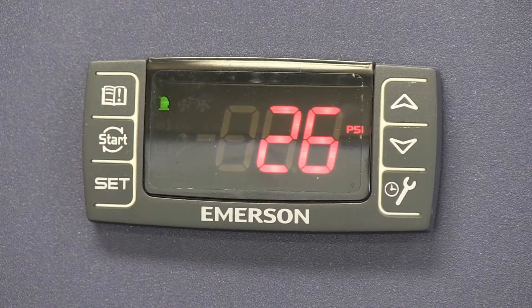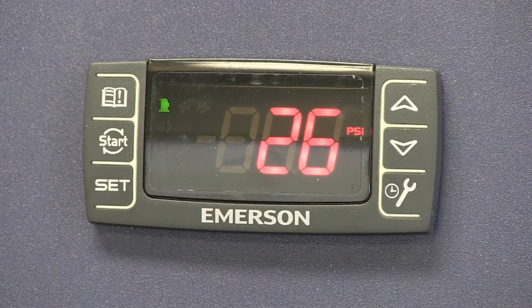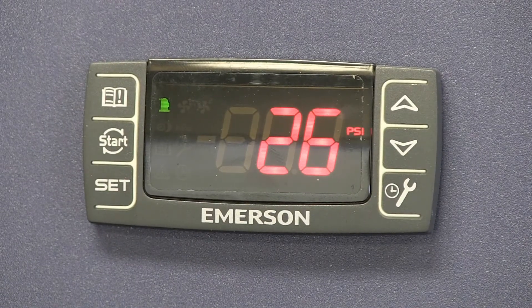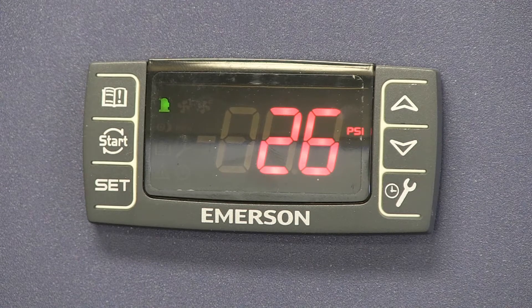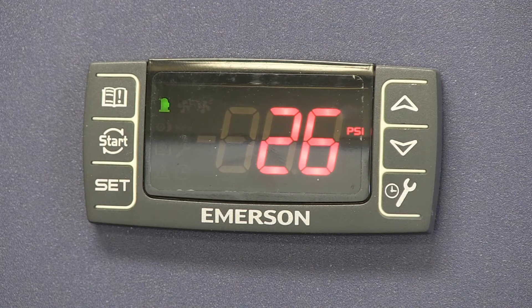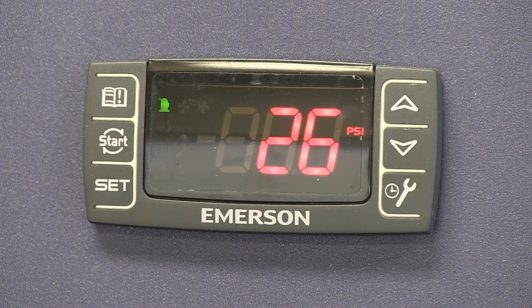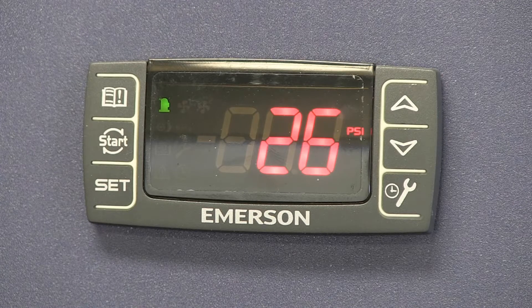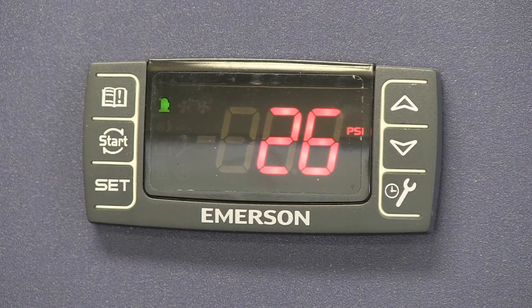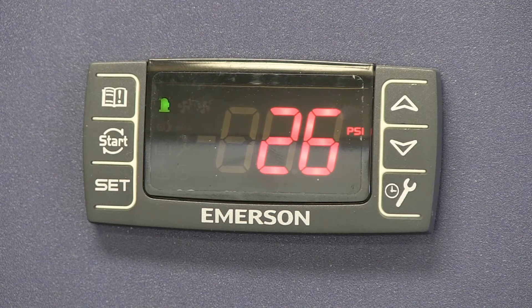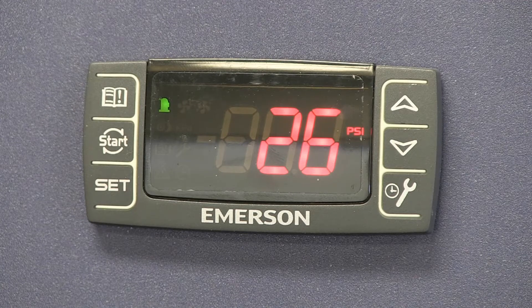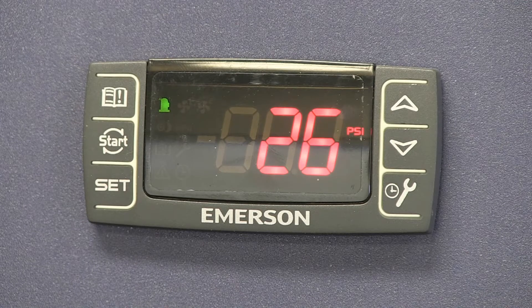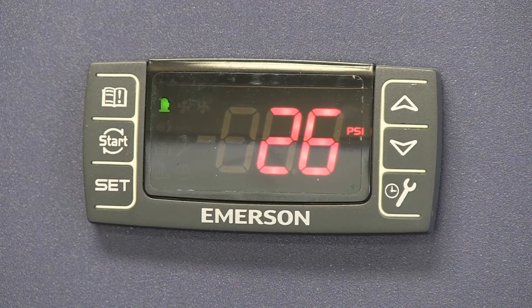The Emerson electronic unit control comes factory set to control units with the condensing temperature usually right around 70 to 90 degrees. If you have an application where that is either too high or too low, there are parameters that you can adjust to change that setting.